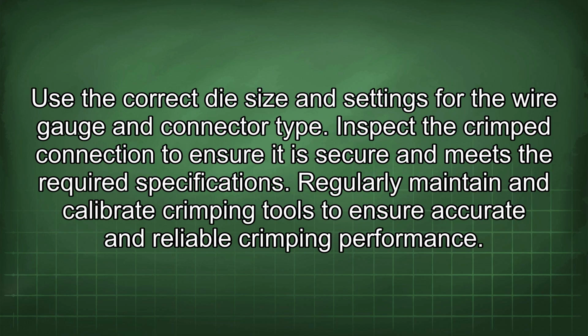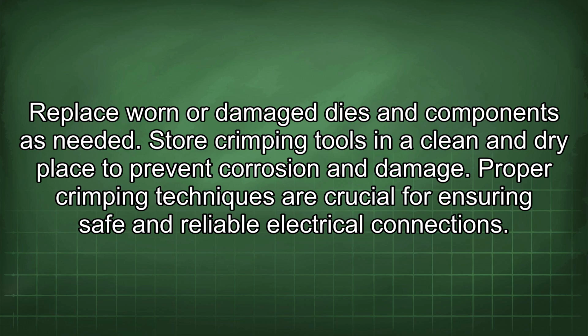Use the correct die size and settings for the wire gauge and connector type. Inspect the crimped connection to ensure it is secure and meets the required specifications. Regularly maintain and calibrate crimping tools to ensure accurate and reliable crimping performance. Replace worn or damaged dies and components as needed. Store crimping tools in a clean and dry place to prevent corrosion and damage.